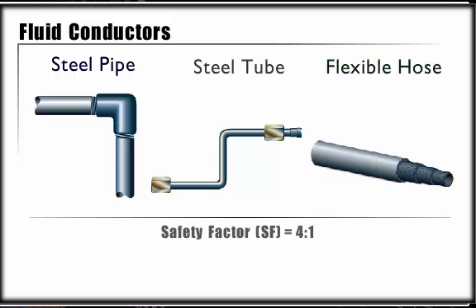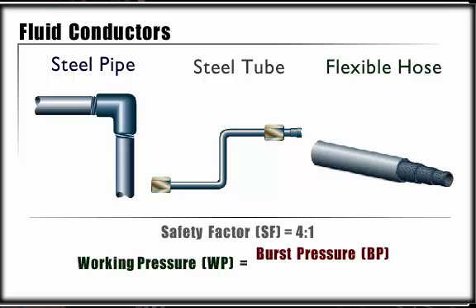A safety factor of 4 to 1 is recommended on the pressure rating of the plumbing material. To determine the working pressure of the conductor, we must take the rated burst pressure and divide by the safety factor of 4.